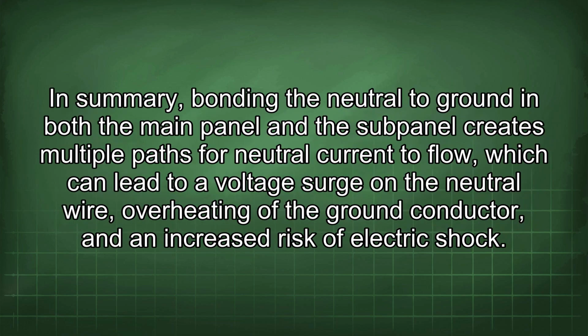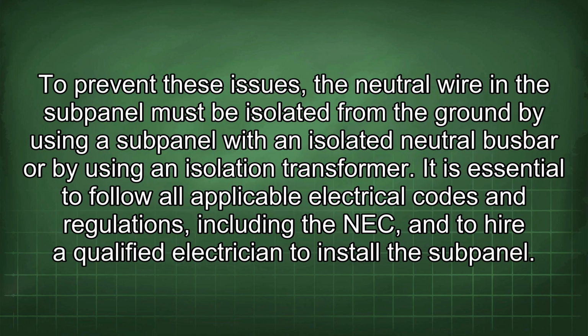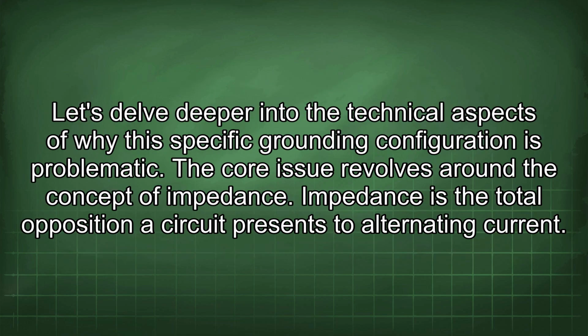In summary, bonding the neutral to ground in both the main panel and the subpanel creates multiple paths for neutral current to flow, which can lead to a voltage surge on the neutral wire, overheating of the ground conductor, and an increased risk of electric shock. To prevent these issues, the neutral wire in the subpanel must be isolated from the ground by using a subpanel with an isolated neutral busbar or by using an isolation transformer. It is essential to follow all applicable electrical codes and regulations, including the NEC, and to hire a qualified electrician to install the subpanel. Let's delve deeper into the technical aspects of why this specific grounding configuration is problematic.